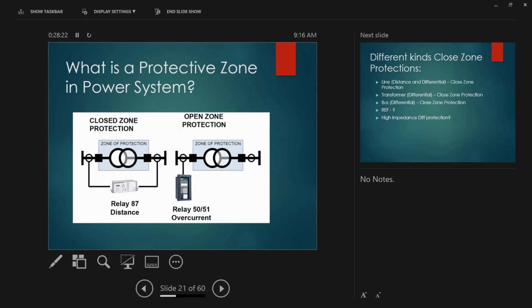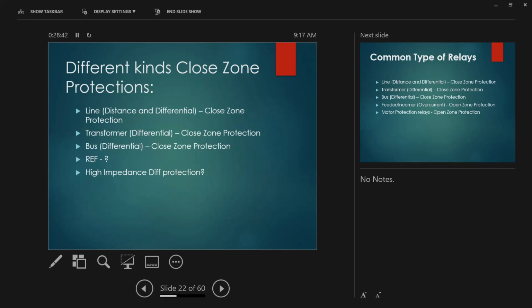Multifunction. Unlike those days, one door is full of relays. In my time, it's just ridiculous. But now, because of the advancement of technology, the relay can be reprogrammed depending on the application. Okay? So yeah, different kinds of zone. If you look at line differential, yes, that's closed zone because it's only looking at the differential. Transformer differential, closed zone as well. Bus differential is closed zone as well. Just to give you an idea how to identify this specific protection.